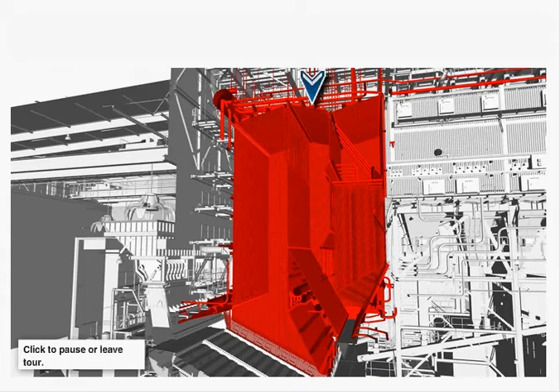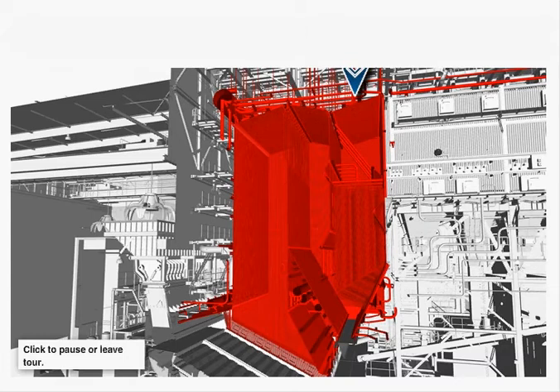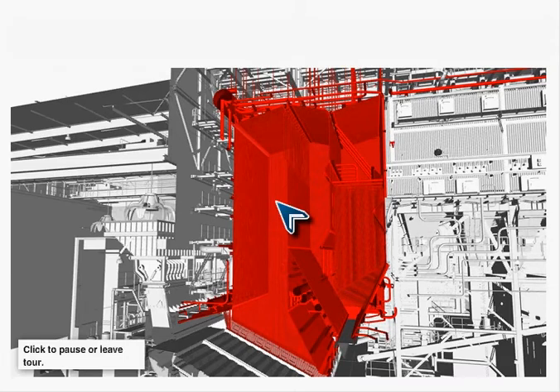In order to ensure high availability, we use our Volund online boiler washing system. The boiler washer is fully automatic and able to clean radiant passes quite efficiently. Therefore, we can control the inlet temperature to the convection part and reduce the risk of corrosion. Our multi-pass boiler has three empty radiant passes. In this section of the boiler, the dominant heat transfer is by thermal radiation.